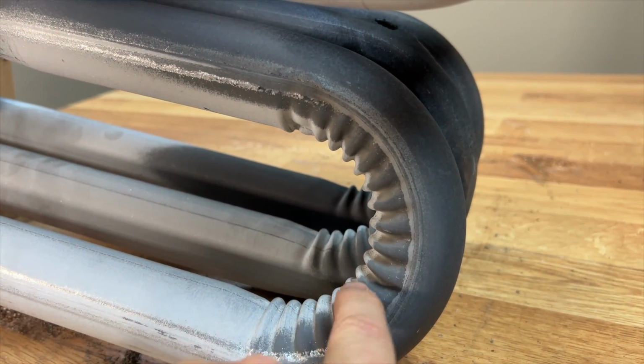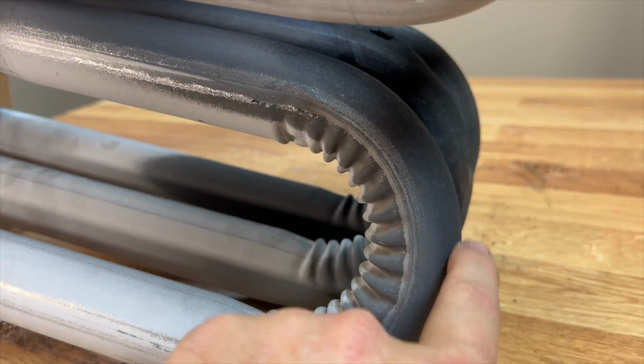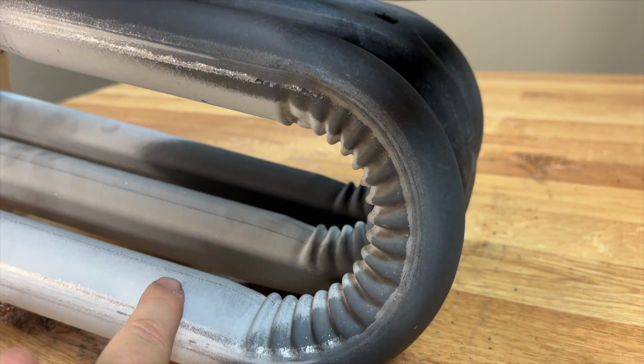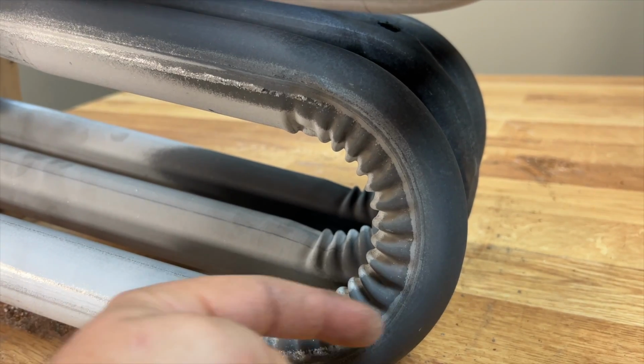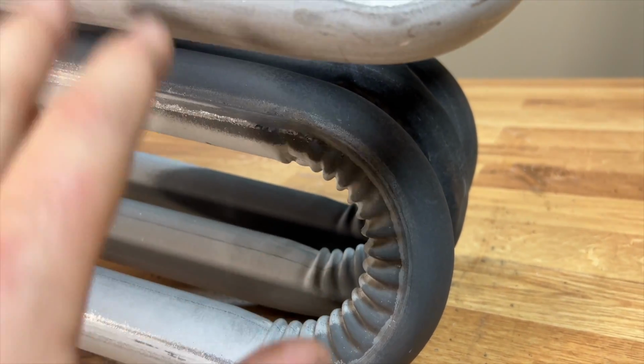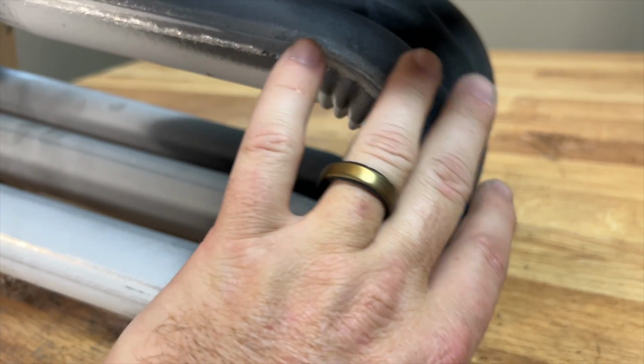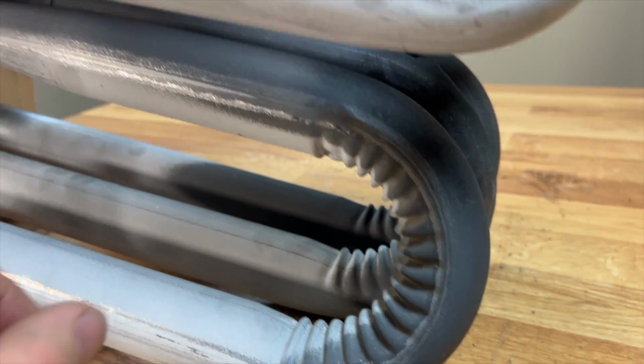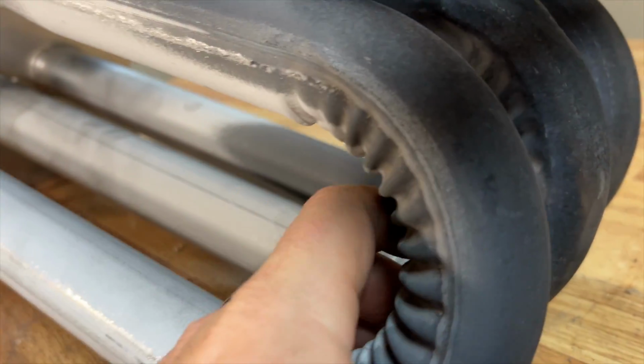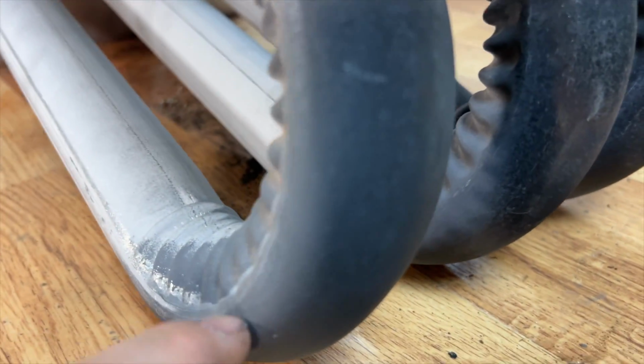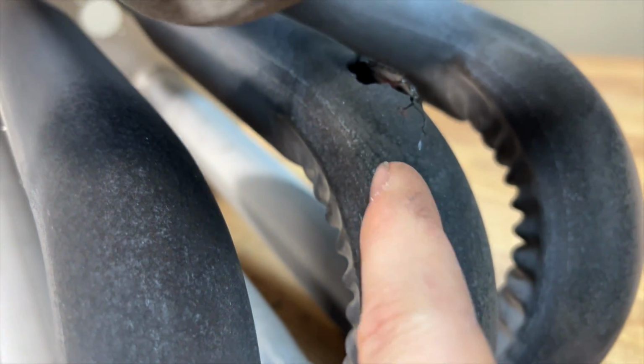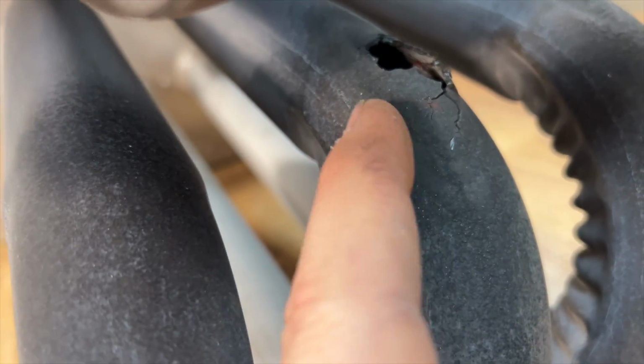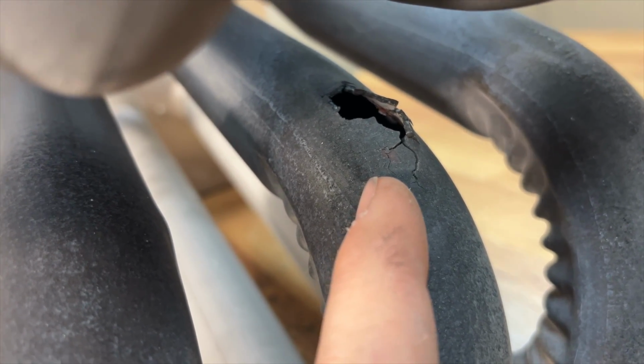Now, on these turns, this is where you're going to see a lot of the temperature stress, and that's just because a lot of that heat's basically hitting the back of it and then turning. So you'll always see the temperature stress, usually on the bends. Now sometimes you might see little random spots here and there, but we can see here that this guy was definitely overfiring. See how dark it is? Now usually the temperature stress is going to be pretty light, like a lighter gray, kind of like this, but you see how it's almost black? So this thing has been really overheated, so I suspect that we had some major overfiring. Probably gas pressure was too high.